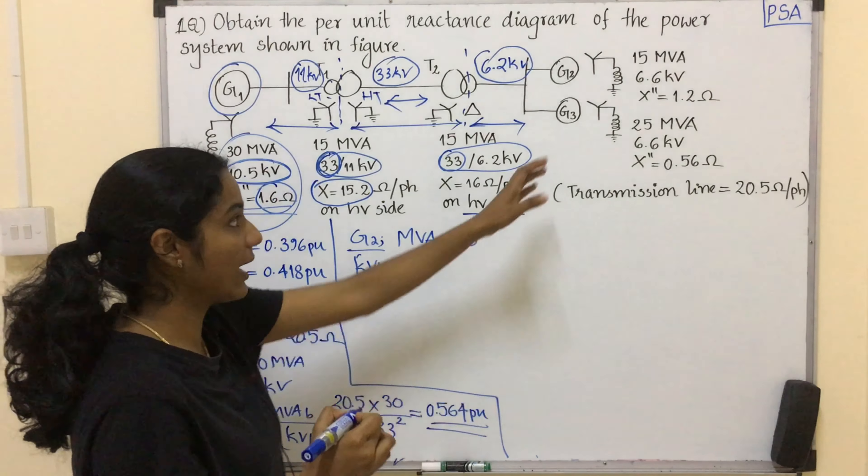This formula uses all elements. Per-unit values are easy to calculate again. In the previous case, generator 1 values are the common base values. The conversion formula is: X per unit new equals X per unit old multiplied by (MVA base new divided by MVA base old) multiplied by (KV base old divided by KV base new) squared.